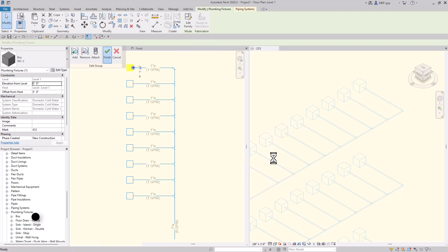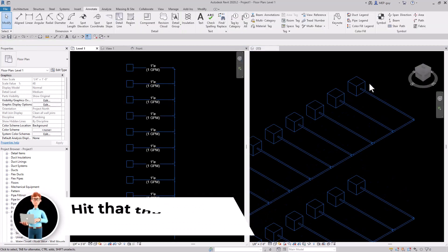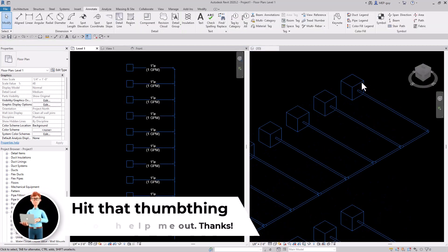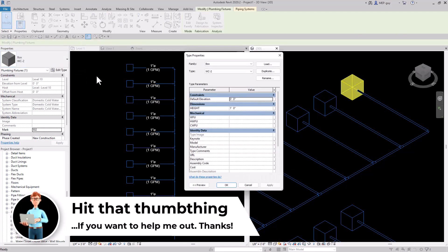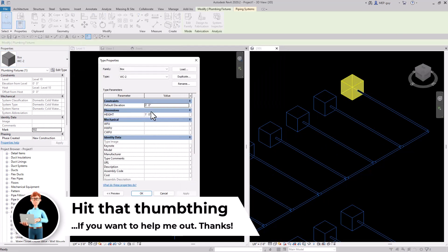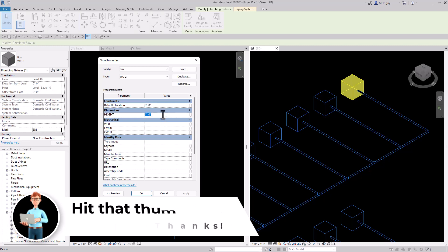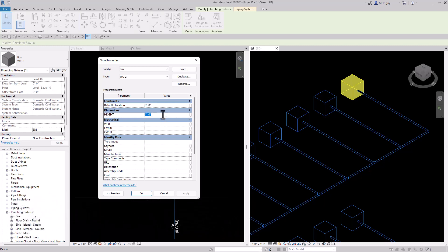Now I can tab into this fixture in my 3D view, go to edit type, and use that height parameter I created. I'll make this 17 inches because that's the minimum height for an ADA fixture and click OK.